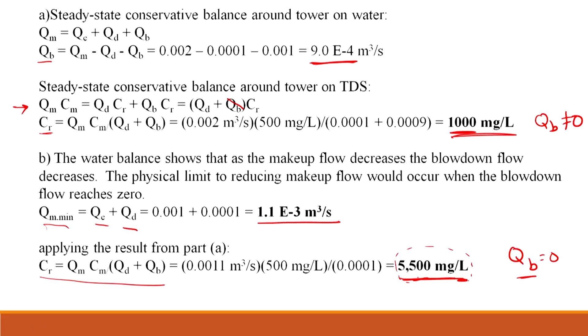Compare that with the TDS in the recirculating water from part A, where Q blow down was not equal to 0, versus here where Q blow down equals 0. So you see the need for bleeding water from time to time from the recirculating flow within the cooling tower. Otherwise, you will have increasing TDS, or with respect to hardness as we saw earlier, you will have scale formation on the heat exchanger, leading to huge maintenance losses.